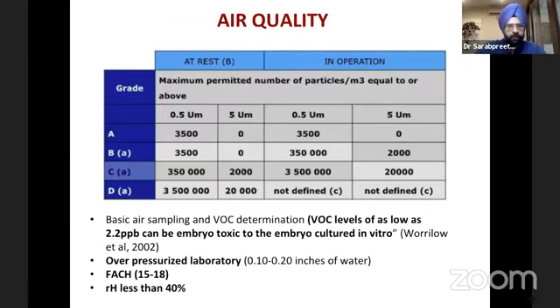VOC levels as low as 0.2 parts per billion can be embryotoxic. The lab should be overpressurized. It should be able to flush out all the VOCs and contaminants. The frequency of air changes should be at least 15 to 18, with a relative humidity of 40% and temperature of around 25 degrees Celsius. This is the optimal air quality which will help you optimize your culture media results and overall culture system results.